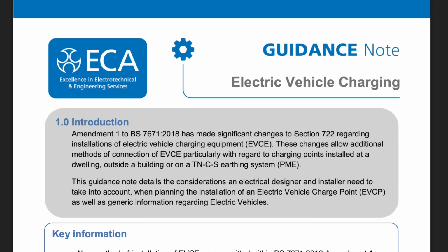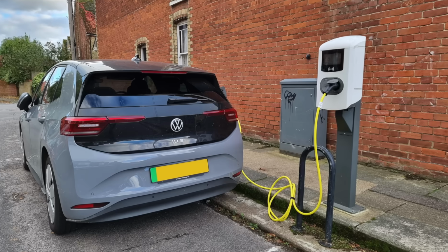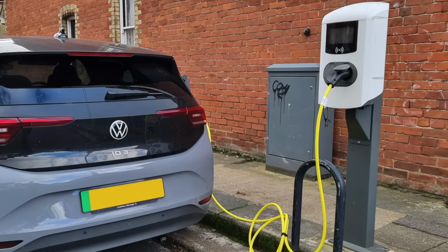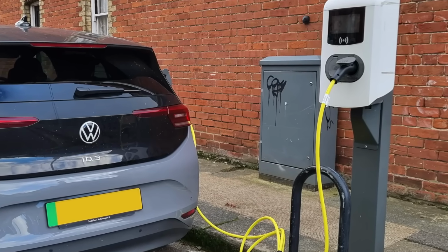Consultant engineer and chairman of the IET Wiring Regulations Policy Committee, Graham Kenyon, pointed out to us at the time that under the IET's Code of Practice for Electric Vehicle Charging Equipment Installation, electricians should carry out a simultaneous contact assessment before starting an install. Guidance on EV charging from the Electrical Contractors Association also emphasises the need for such an appraisal. If you can touch any other electrical equipment at the same time as the electric vehicle, you need to ensure that it's connected to the same earthing system.